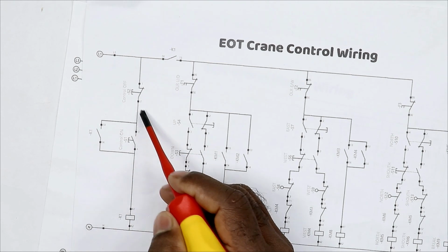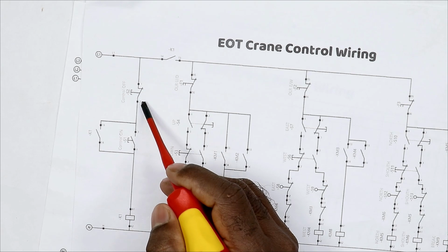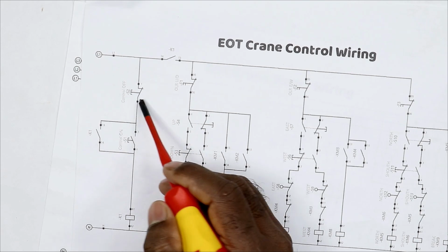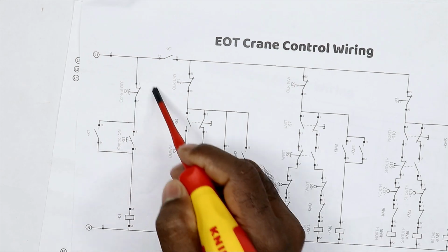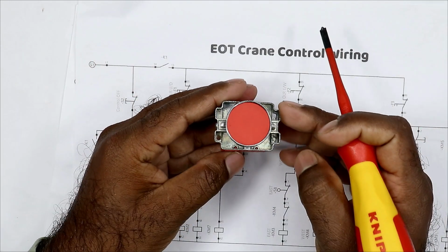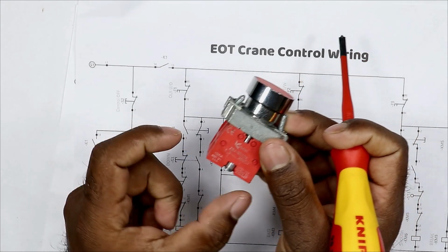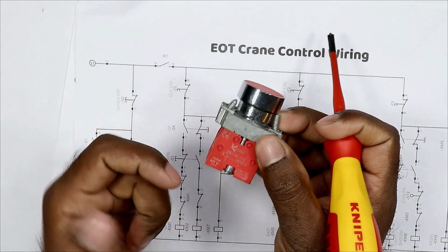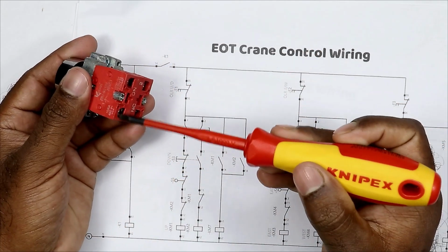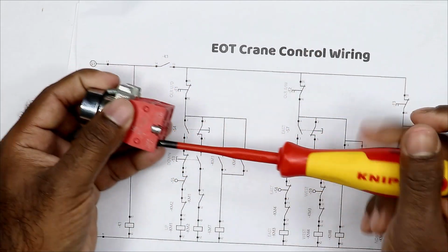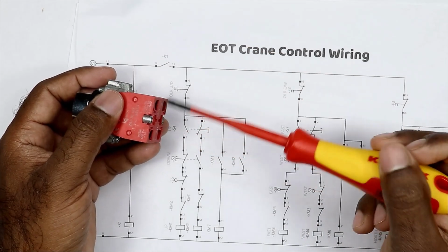In this condition, what we will do is connect the multimeter here and press the push button 2 to 3 times to check whether power supply is coming or not. If power supply is not there, then we will check the wire connected here. Besides the stop push button, there is an element connected at the back side, and we have to check this. We will first check the wire connected with this element and see whether there is any loose connection or not. If found loose, tighten all the connections, and due to this, the remaining motor may start working.